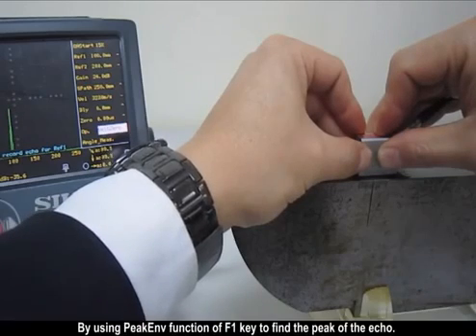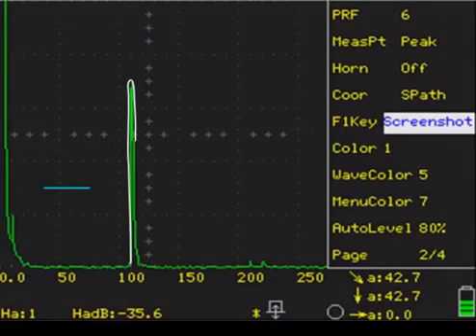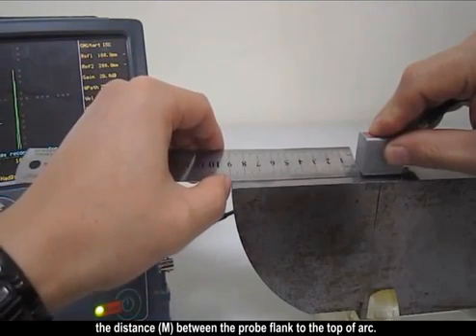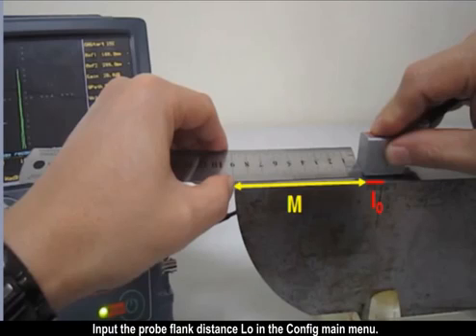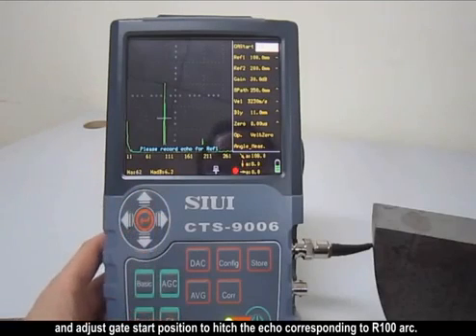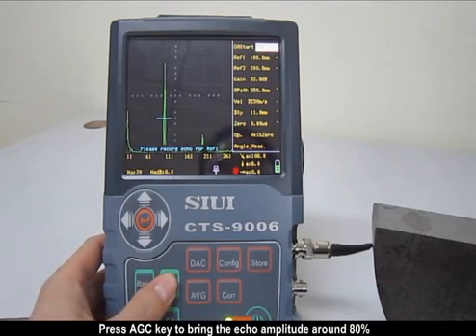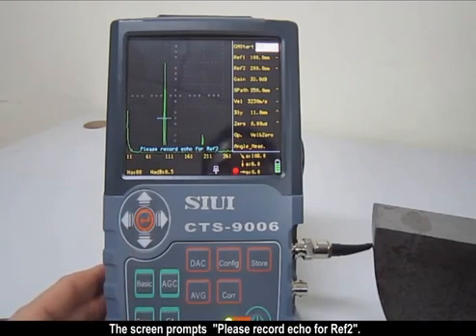Find the peak of the echo by moving the probe, using the peak envelope function of the F1 key. Hold the probe and use a ruler to measure the distance M between the probe flank and the top of R; the probe flank distance L0 is 100–M. Input the probe flank distance L0 in the configure main menu. Hold the probe and adjust gate start position to hit the echo corresponding to R100. Press the AGC key to bring the echo amplitude to around 80%, then press the confirm key.